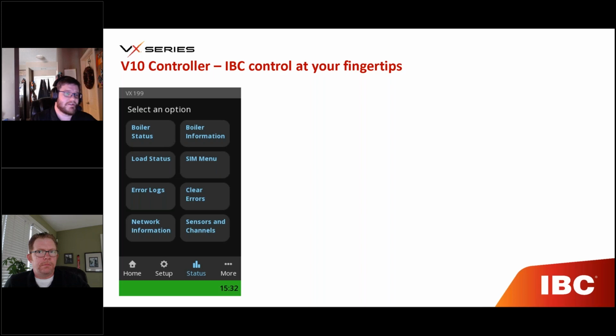Error logs are kind of self-explanatory—we just went through that. Clear errors is where the boiler will actually reset the safety ignition module as well as the V10 control to a green status and then recheck everything. That allows you to see what's happening and clear out whatever issue you're having. Network information is just a quick check to see if it's connected to the internet.